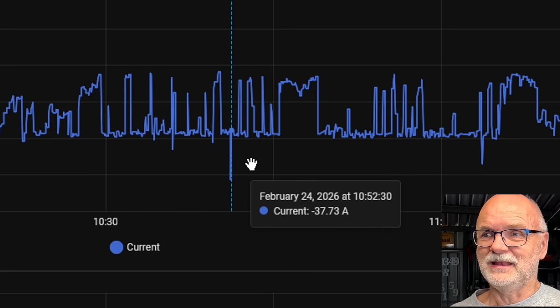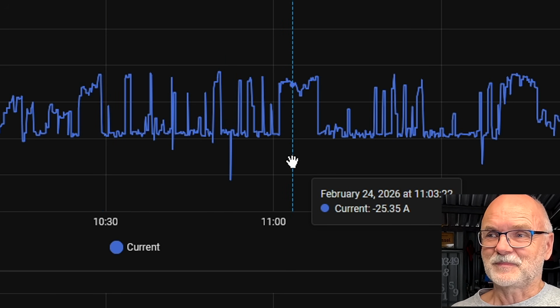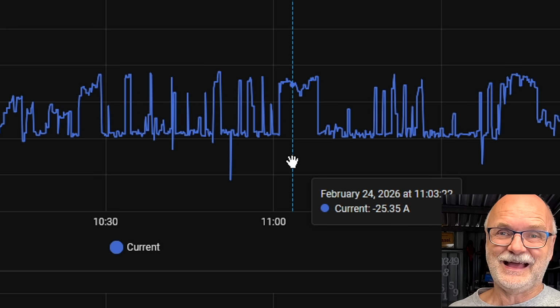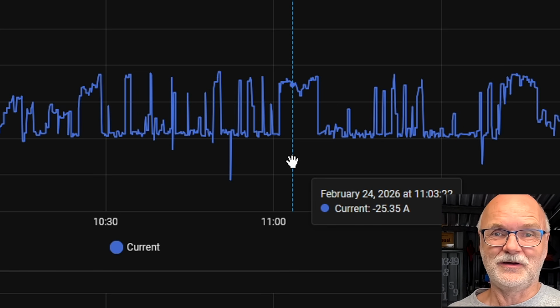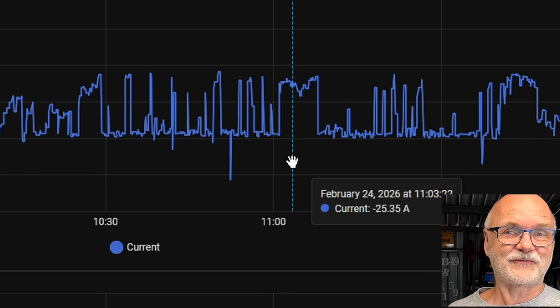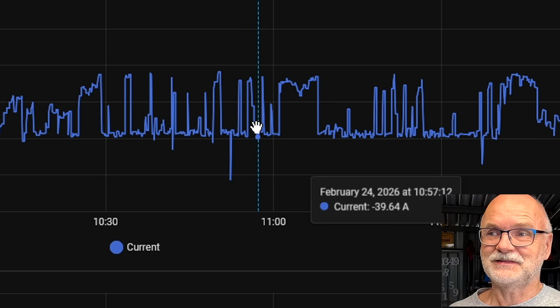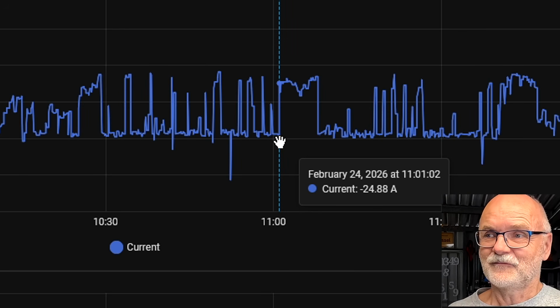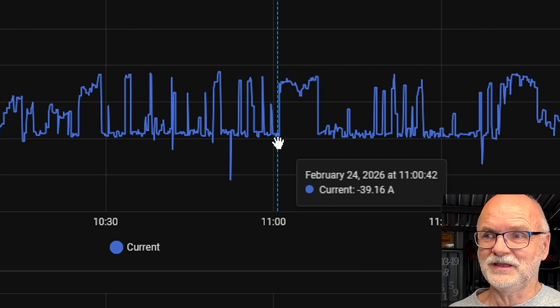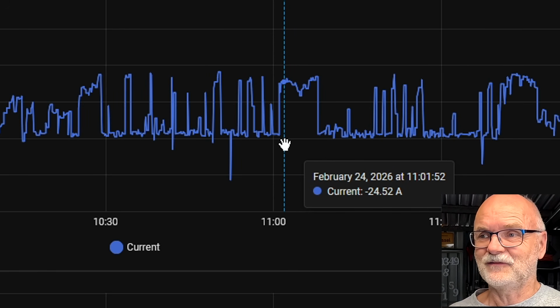It gets really noisy, and what you can see here is a cloudy day. This is when the solar kicks in and takes over the inverter load. If the tilt system produces 1.5 or 2 kilowatts, we're using less from the battery, obviously, and you can see the current goes down from negative 40 almost to negative 24.